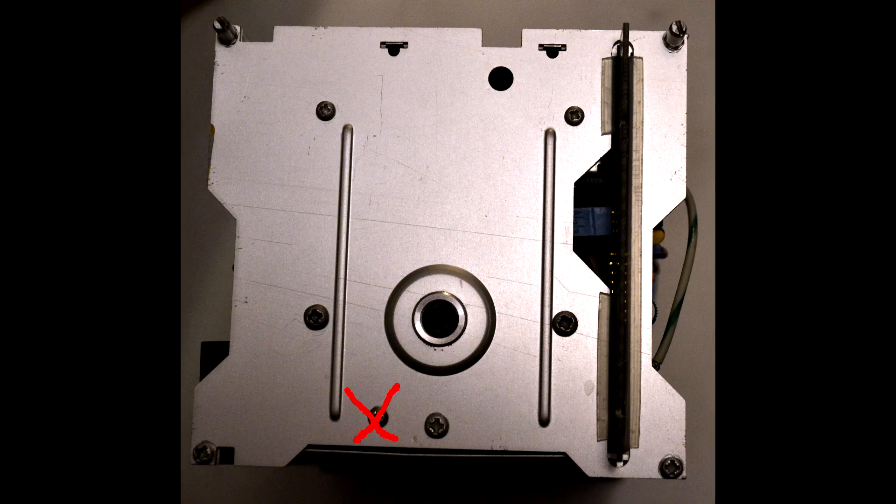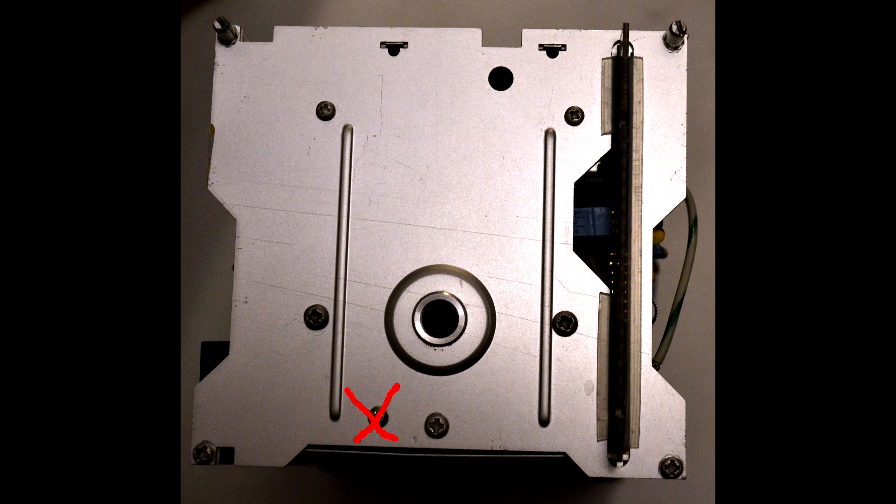Before removing the auxiliary board, remove the back panel. Remove nine screws from the back panel, but not the one marked here. It holds the pass transistor for the 5 volt supply.